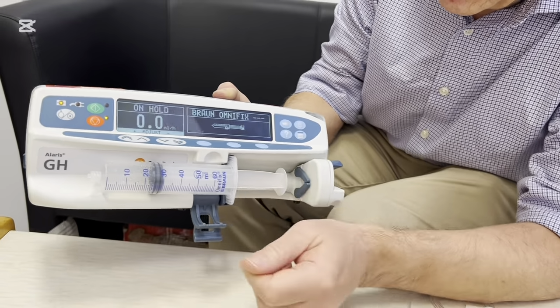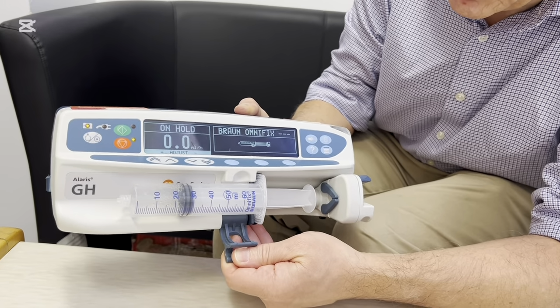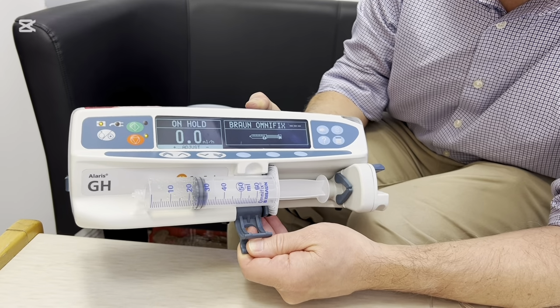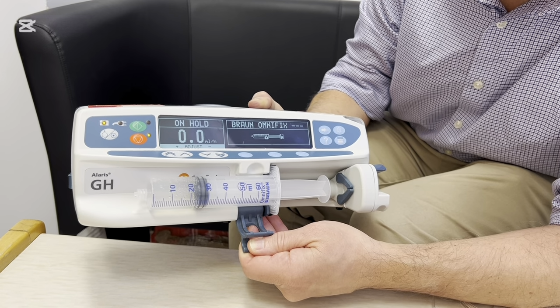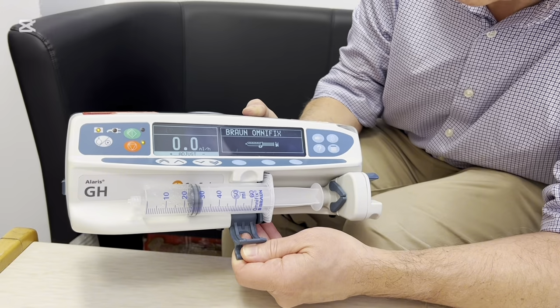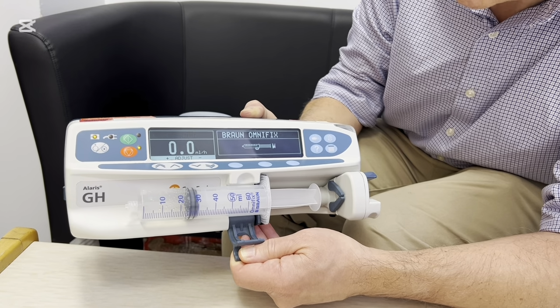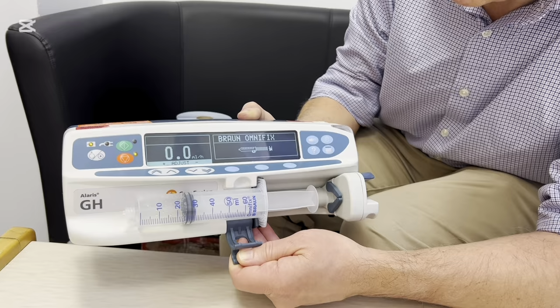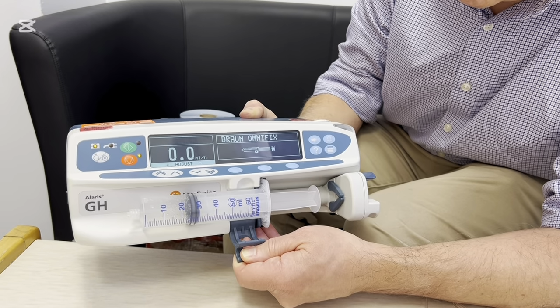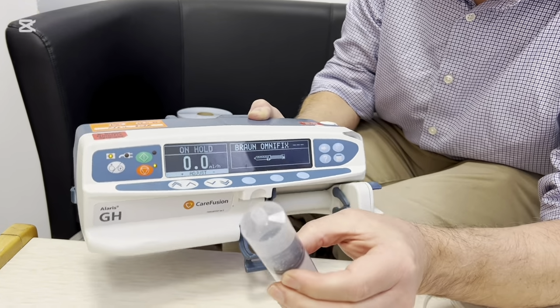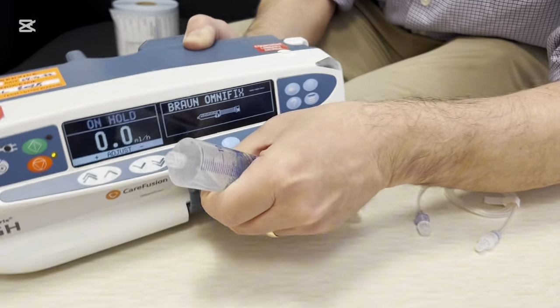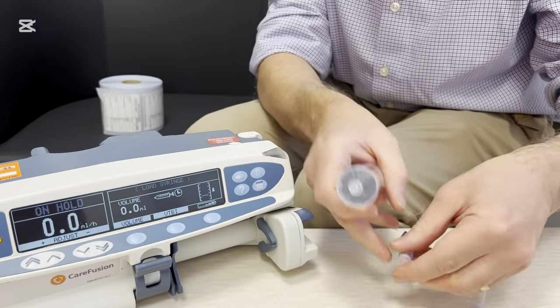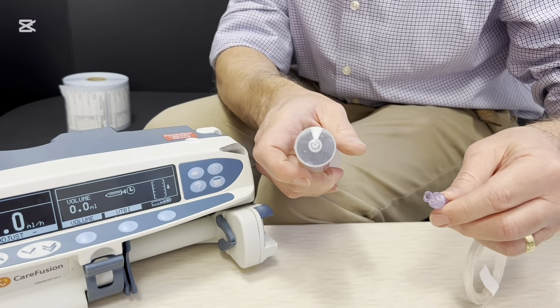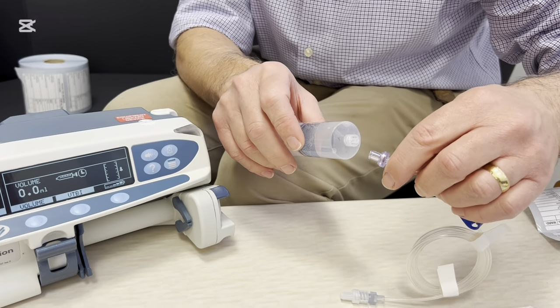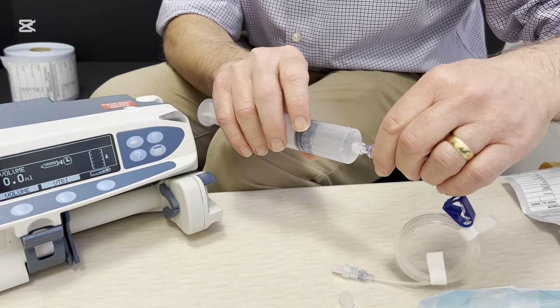So all these syringe pumps, or all volumetric syringe pumps, can potentially have a range of syringe types within their library. And depending on where you work, some hospitals may have their libraries open, so you can select any number of syringes. We've locked ours down so that it only accepts, or is calibrated only to use, Braun Omnifix syringes. What you'll notice about this syringe is that it's a Luer lock device rather than a Luer slip. So whenever you're using a syringe pump, you should always use a Luer lock so that the administration set doesn't inadvertently slip off the syringe and then fail to administer the drug that you want to give.